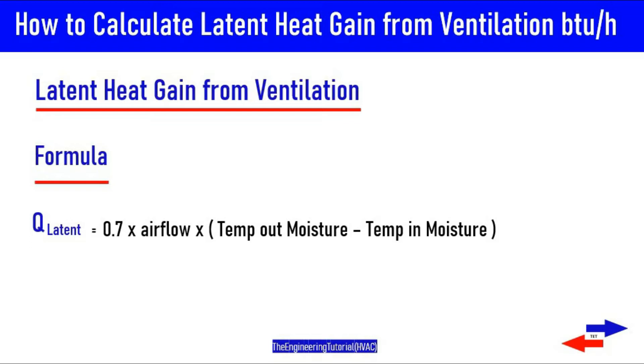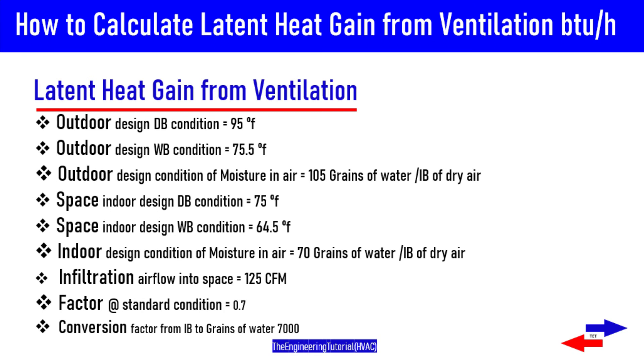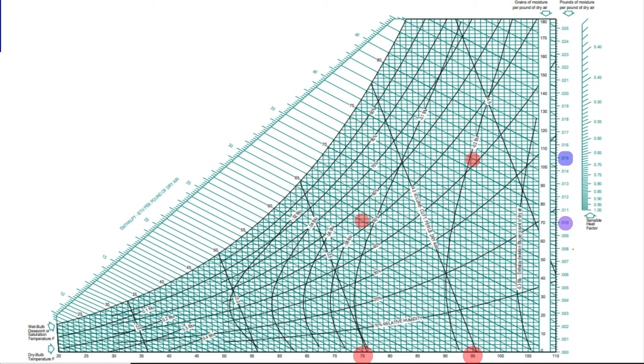The equation is: QL = 0.7 × airflow × (humidity ratio outdoor − humidity ratio indoor). The constant 0.7 is derived from the properties of dry air at standard conditions — 69°F dry air at sea level. Air at other conditions and elevations will cause these factors to change.